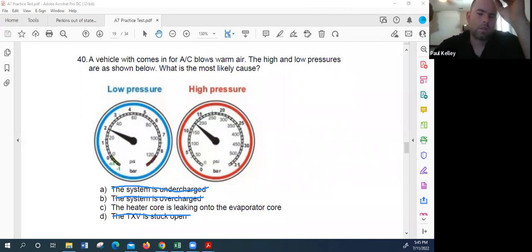You're close, you're close, I'm gonna get you there the rest of the way. If your AC is blowing warm, the first thing you're gonna want to look at is your pressures, and you're expecting your pressures to be jacked up, because if your pressures are jacked up, it's not going to cause the forced condensing and the evaporation it's supposed to cause.